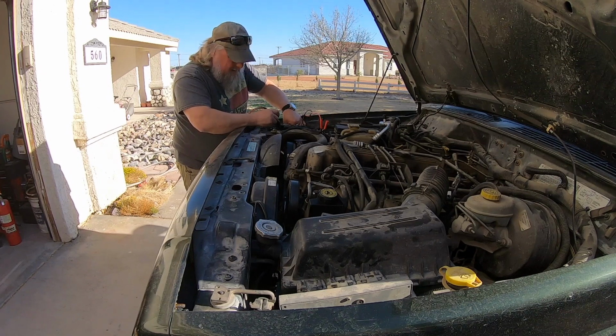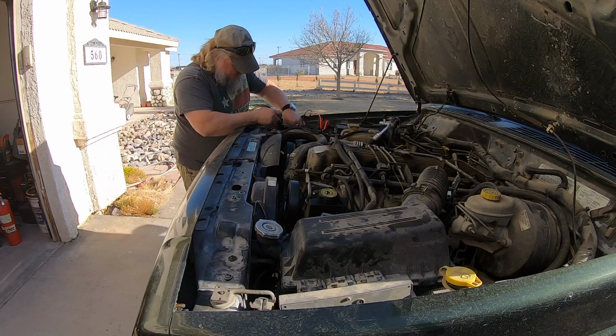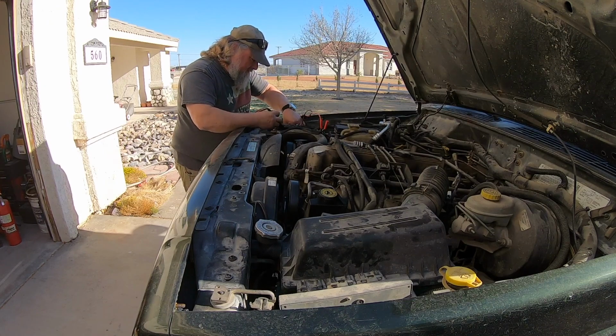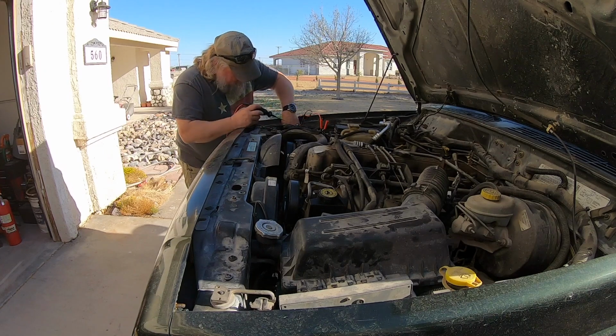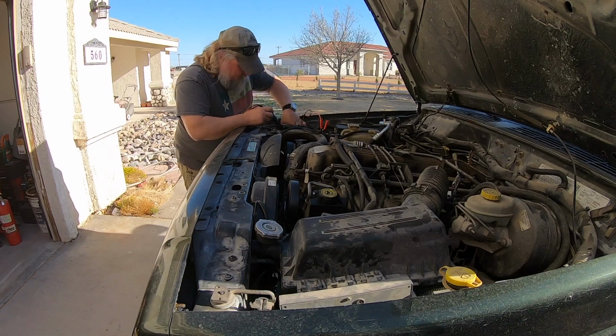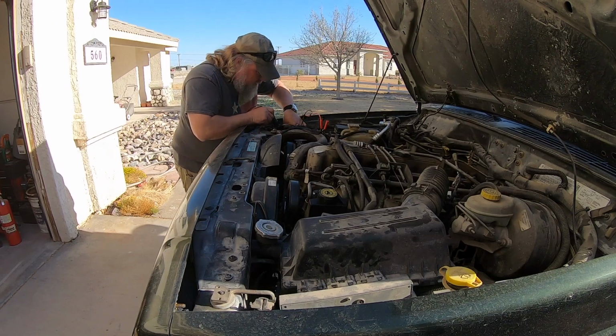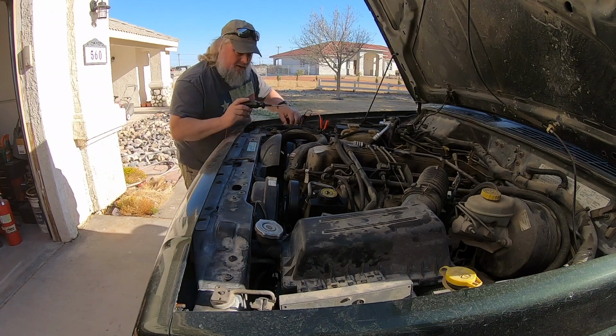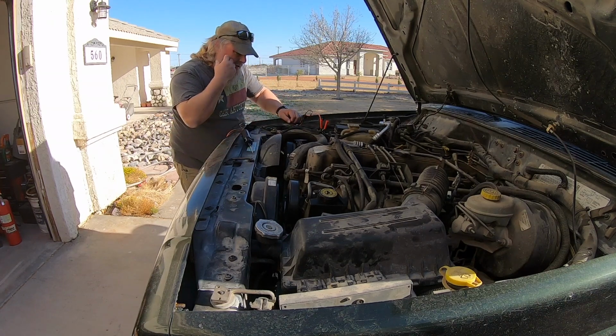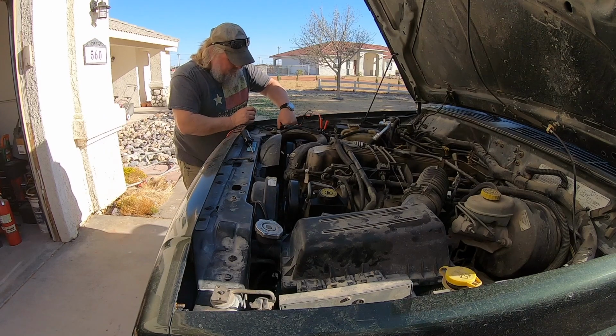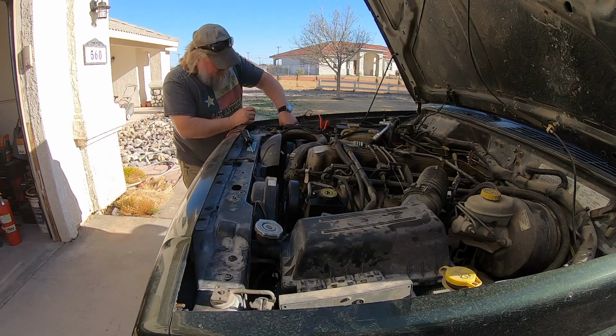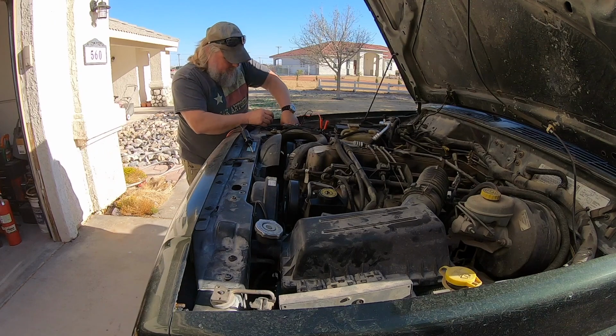So I can put that right on the energize position and energize that relay using my power probe. At the same time, once I plug it in, it shows me a green light, confirming continuity. So if there was something wrong with the relay, first of all, it wouldn't energize once I put power to the connector.